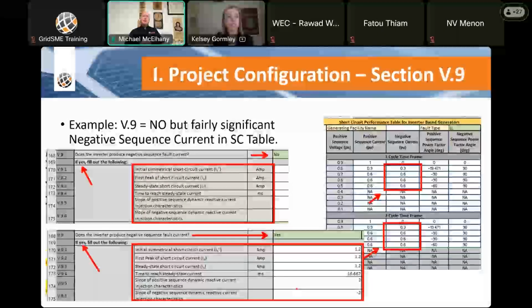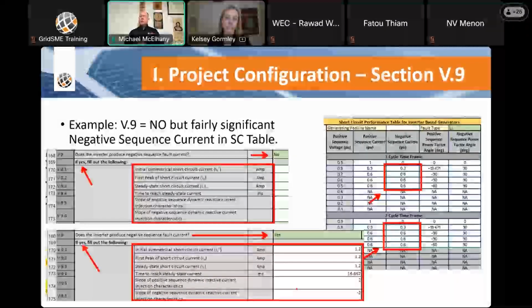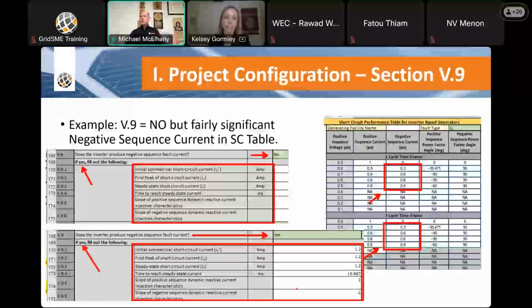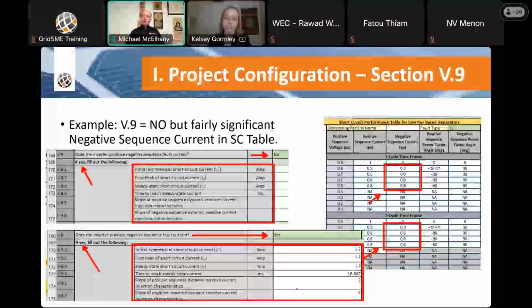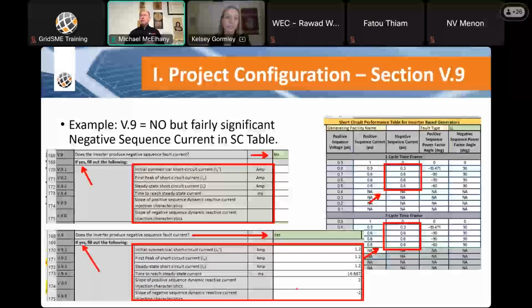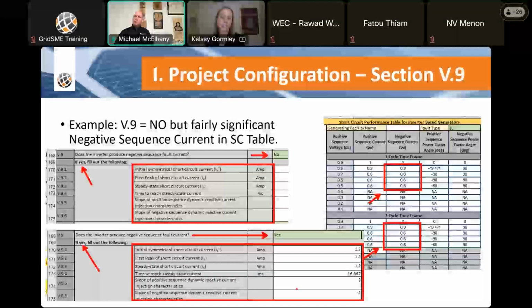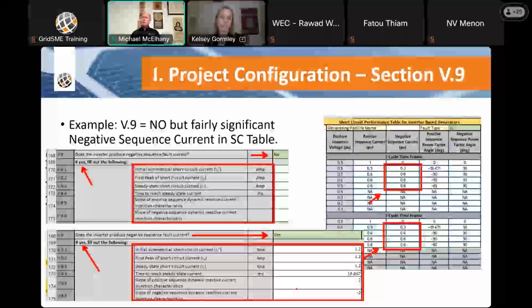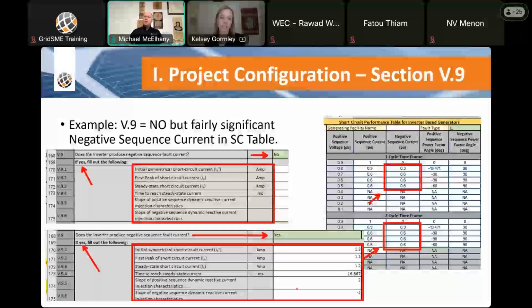So that's an age-old issue that for sequence of events, if you do not have simultaneous time sync to all of your devices that are then recording information, how do you put together what happened first? And so the short answer is yes. And that's one of the reasons that there is some concern that network time protocol does not have the guarantee of that, as opposed to precision time protocol or direct injection of time sync into an inverter specifically, like through a direct IRIG-B interconnection. But the answer is that's the point of it, because otherwise you have a bunch of data that said what an inverter did, which inverter did it first. You'd have no idea if you have no understanding of the simultaneous time sync relative inverter to inverter.